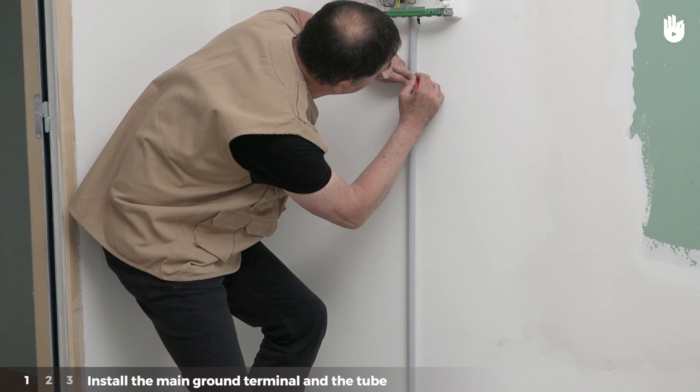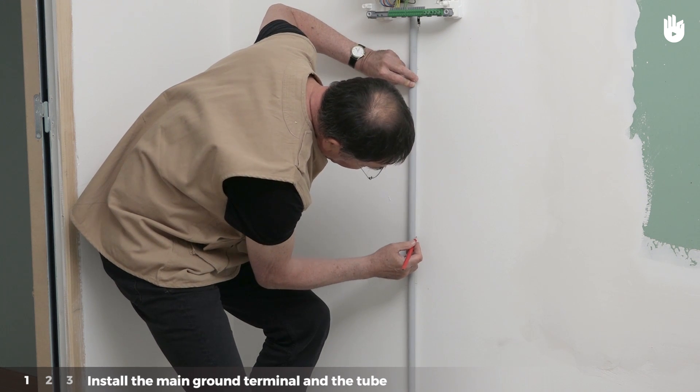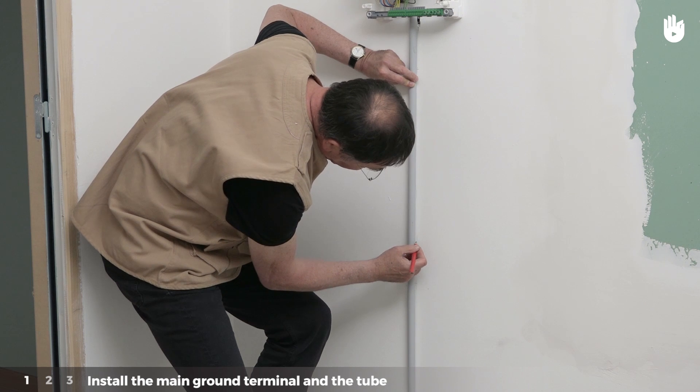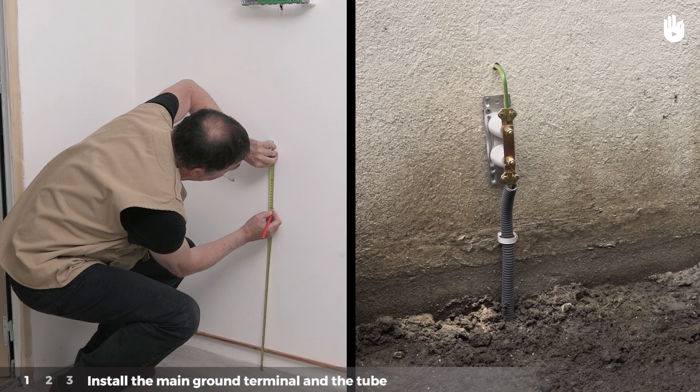Note and mark with the pencil the position of the mounting brackets above and below the tube at most every 80cm. Opposite the disconnecting strip and under the electrical panel, note the location of the main ground terminal.